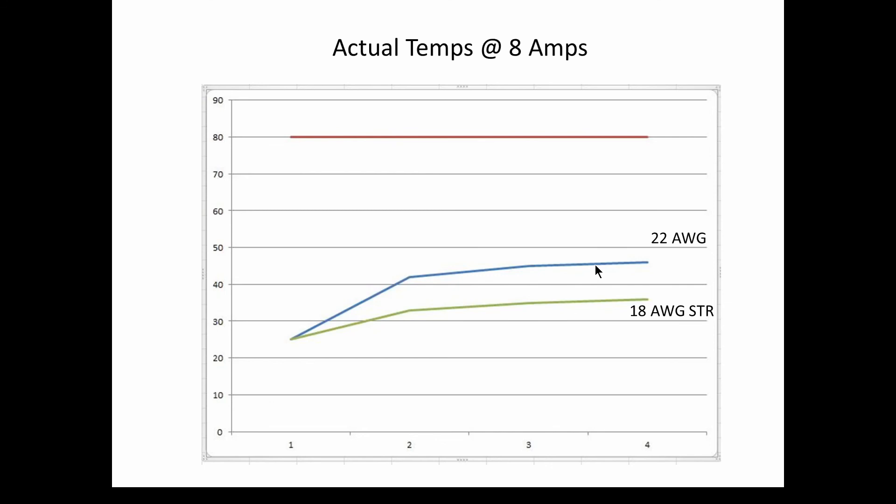So, depending on the situation you're using the wire in, you need to think about what the real limitations are. And you can do testing like I did. You can put a thermocouple and actually measure to get a feel for it. And maybe if you're doing something just for a test, for a couple minute test, maybe it's not a big deal. But my only point here is for you to think about what's behind all this and get a little bit more detailed knowledge about what's going on instead of just assuming that somebody says something and you'll believe it.